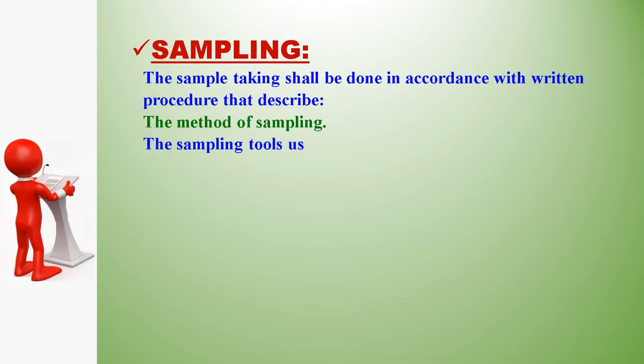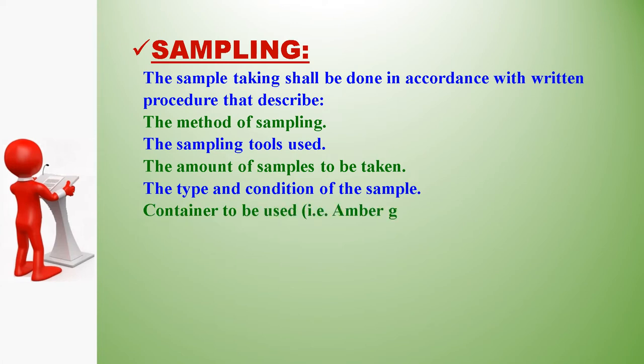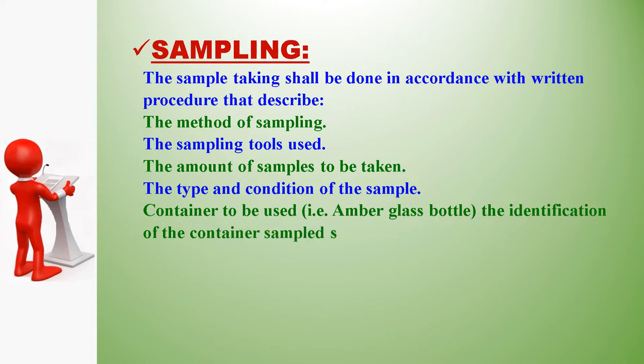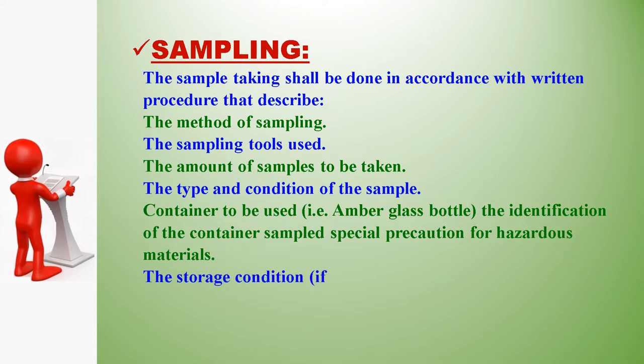Sample taking shall be done in accordance with written procedures that describe the method of sampling, the sampling tools used, the amount of samples to be taken, the type and condition of the sample container, special precautions for hazardous materials, storage conditions if any, instructions for cleaning and storage of sampling equipment, and instructions for resealing open containers.